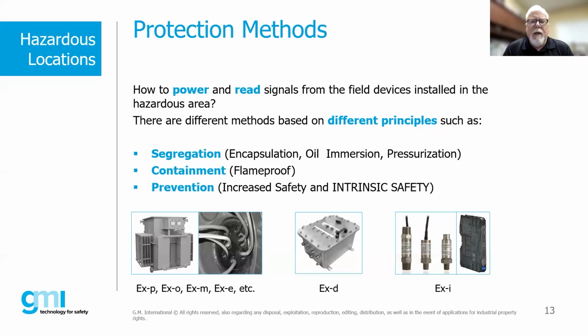Containment is more or less a protection concept that's been around many years, very successful. That's flameproof, where we're basically assuming we're going to have a gas air mixture coming into contact with a flammable substance and we have to contain it. We're expecting an explosion to take place inside of either a flameproof or explosion-proof box, and that has to be designed to withstand that internal explosion and continue on safely.